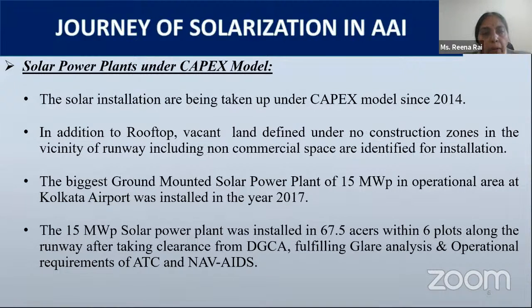Now the solar power plants under CAPEX model are installed at various airports. In addition to rooftop and ground mounted, we are installing ground mounted solar power plants in the operational area. The maximum capacity we have installed, in 2017, is 15 megawatt, in the operational area of Kolkata airport, installed in 67.5 acres of land within 6 plots along the runway, after taking clearances from DGCA and fulfilling glare analysis and operational requirements of ATC and NAVAIDS.